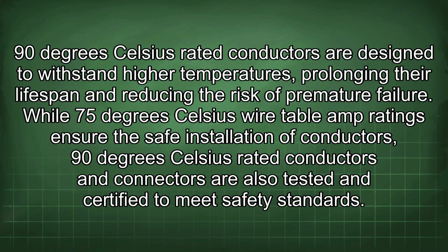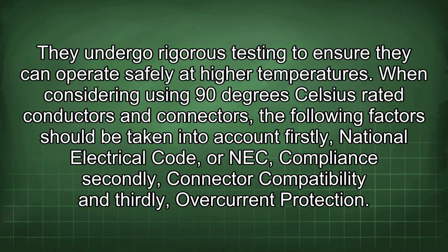failure. While 75 degrees Celsius wire table amp ratings ensure the safe installation of conductors, 90 degrees Celsius rated conductors and connectors are also tested and certified to meet safety standards. They undergo rigorous testing to ensure they can operate safely at higher temperatures.